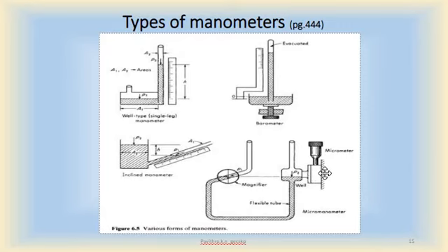Micrometer can record very minute values also. Therefore, by adjusting the level using this micrometer and magnifier, they can be adjusted to very accurate levels. Therefore, this manometer is more accurate compared to others. So in this manometer, the application of unknown pressure difference will cause the level of the fluid to rise above the hairline, but it can be restored to the original point by raising or lowering the well with the micrometer.